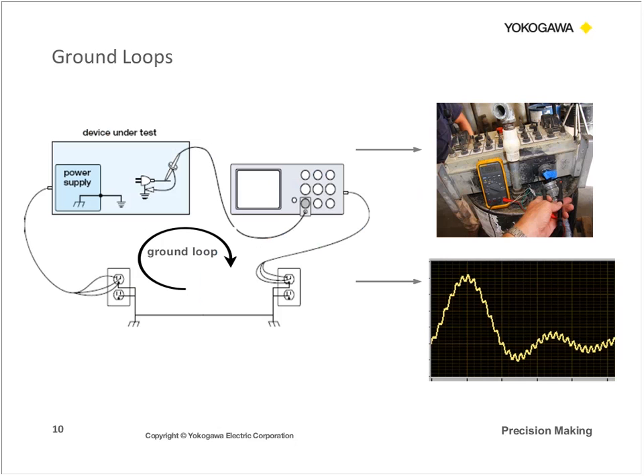Now, a third concern that we need to take care of is ground loops. Ground loops are really the most common noise problem when dealing with high voltage measurements. Especially in large-scale electrical systems, ground loops can stem from poor grounding practices. As a simple example, in plumbing, you sometimes hear of hot water coming out of cold water faucets, even though there's not supposed to be a connection there. But somewhere in the water pipe connection, there was a common point where a crossover happened. And this same surprising result can happen in an electrical circuit where an unintentional ground is introduced at some point in the measuring system. It's not supposed to happen, but a common point to ground was introduced, and this creates a ground loop.